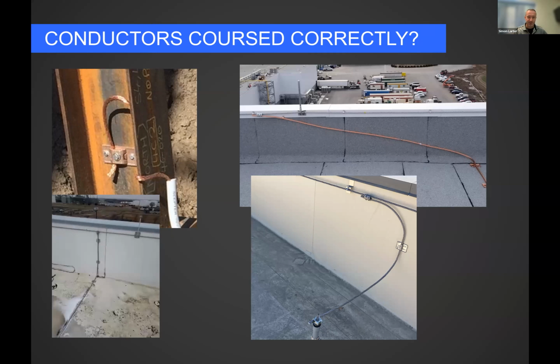So when I did the inspections for both of these, I said, oh no, you've got to change this out. You can't do X, Y, and Z. Keep the bends nice, with a nice sweep radius. You can't go straight up the wall. You have to come up at an angle, but nothing against their qualifications as electricians. They were really good electricians. They just didn't know the lightning protection code. And that's not their fault because nobody ever told them.